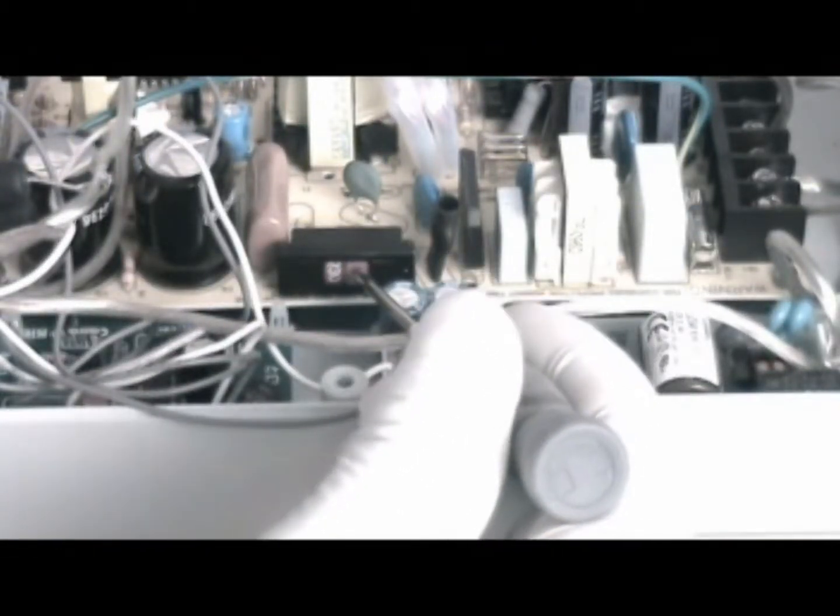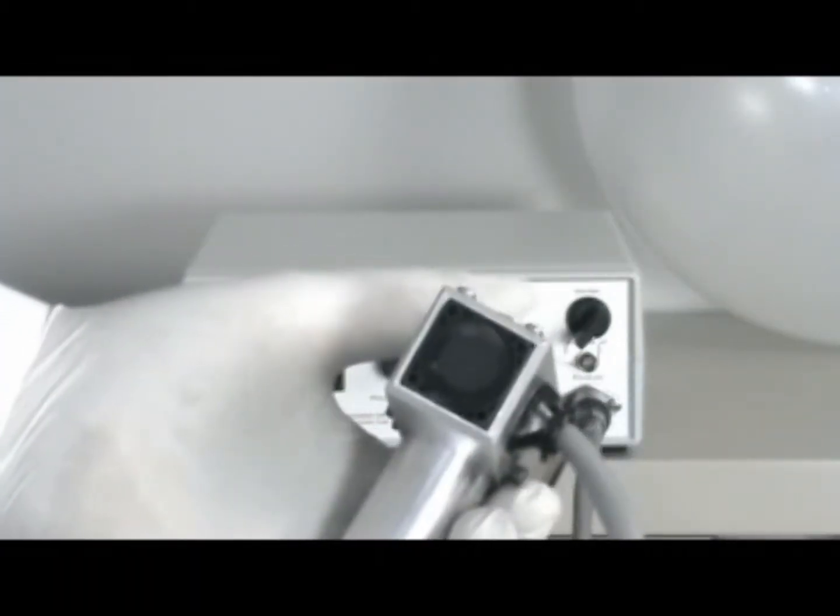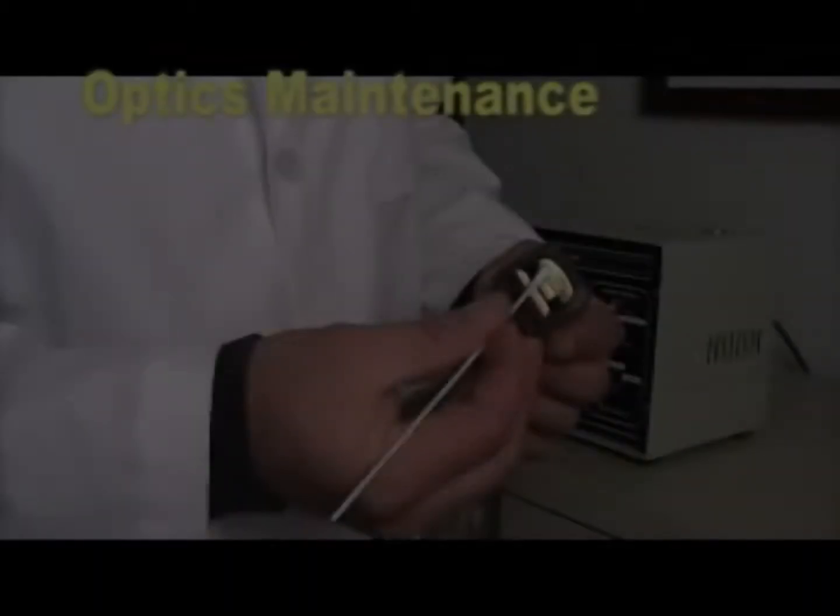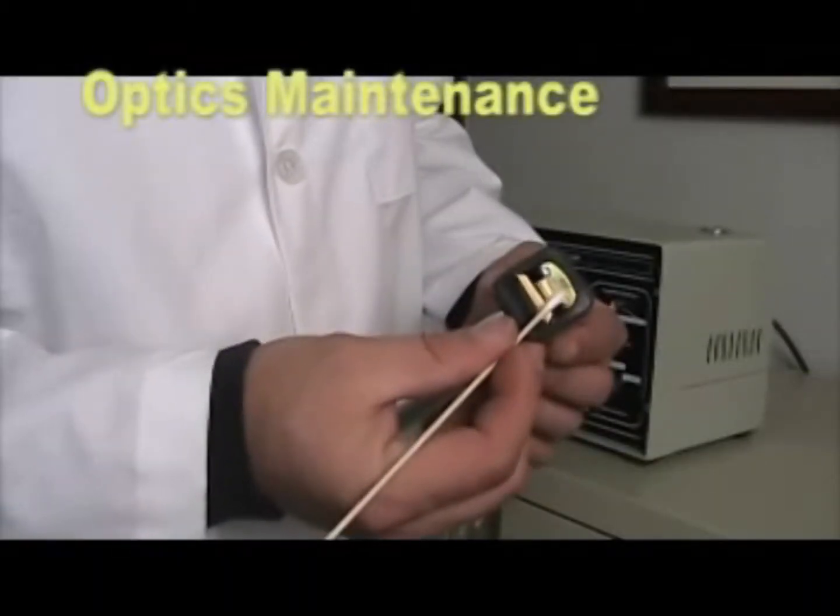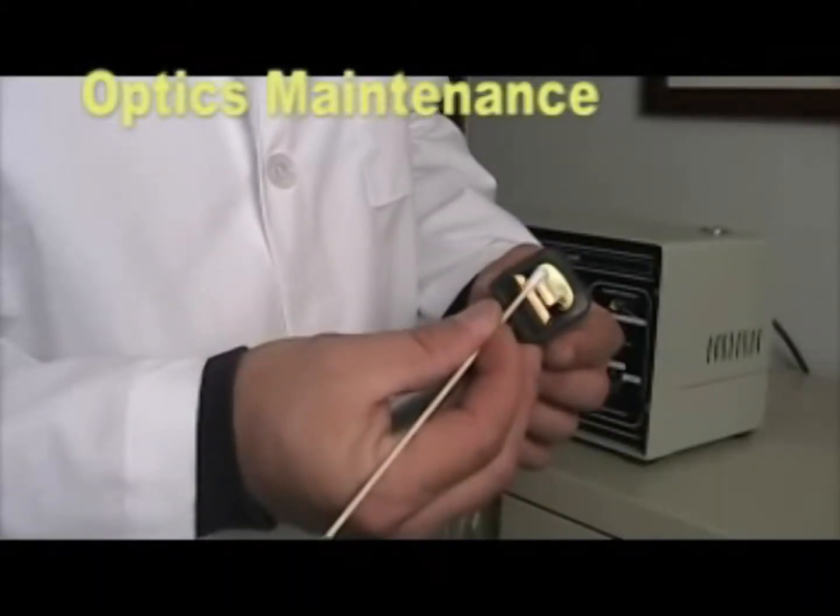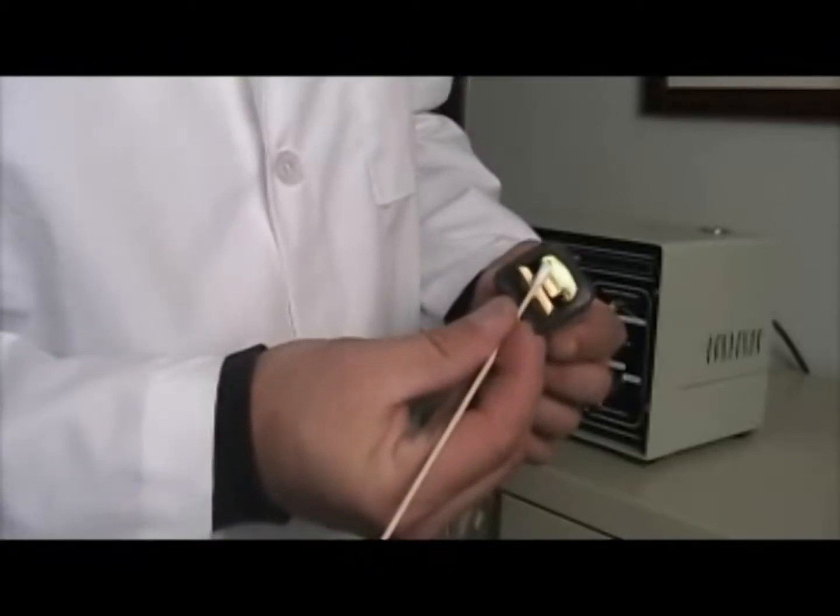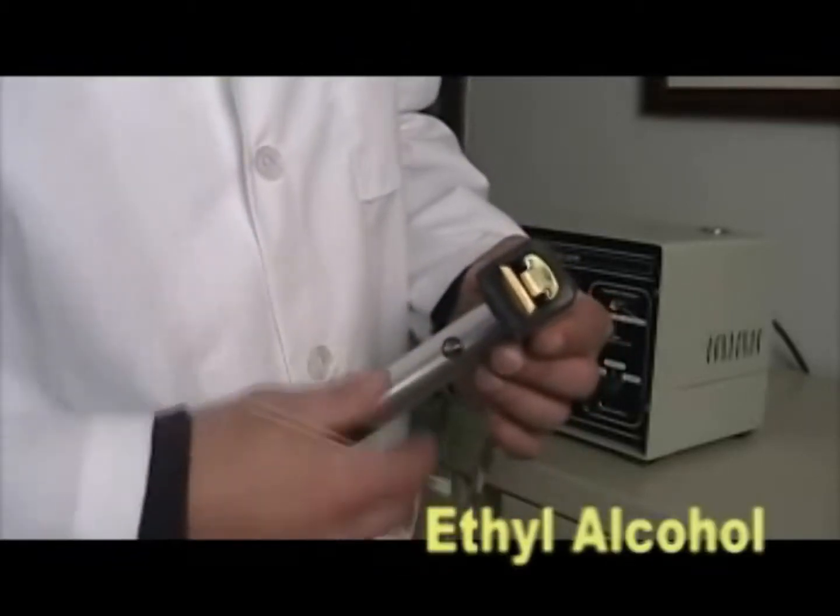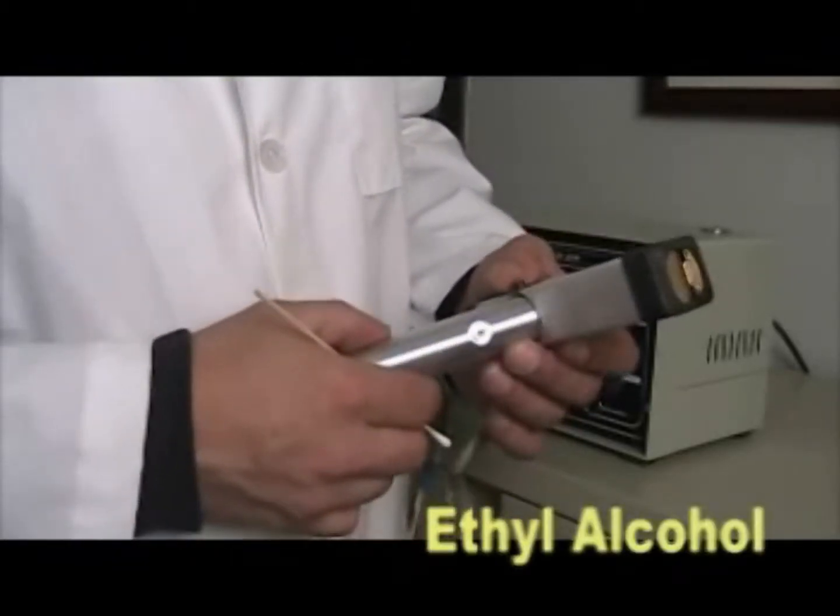Switch to the appropriate voltage, 115 or 230. Make sure your cooling fan is operating without any obstructions. Smoke and vapor from carbonized debris will eventually occlude your lens. It is essential that you keep this lens clean, otherwise serious damage may occur.